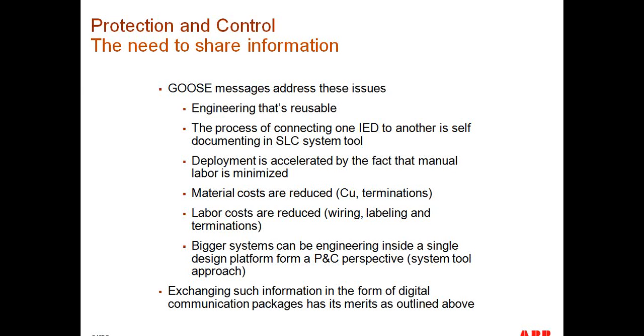The process of connecting one IED to another is self-documented in the substation configuration language tool. In essence, when you configure a GOOSE message in your system tool, the software itself is documenting this association, what's going out from one device and what's coming into another device, essentially replacing logic diagrams of IEDs inside of a substation.